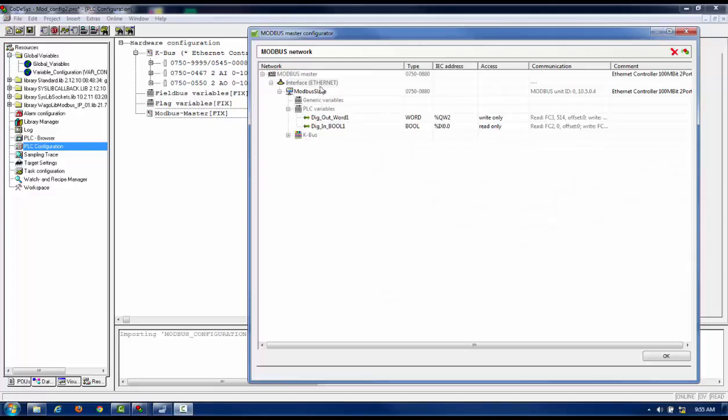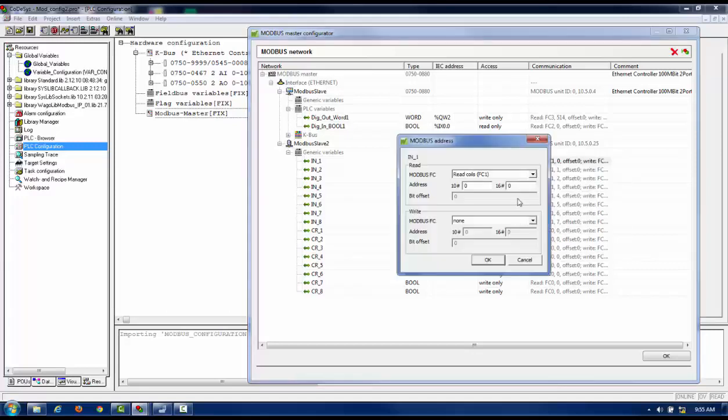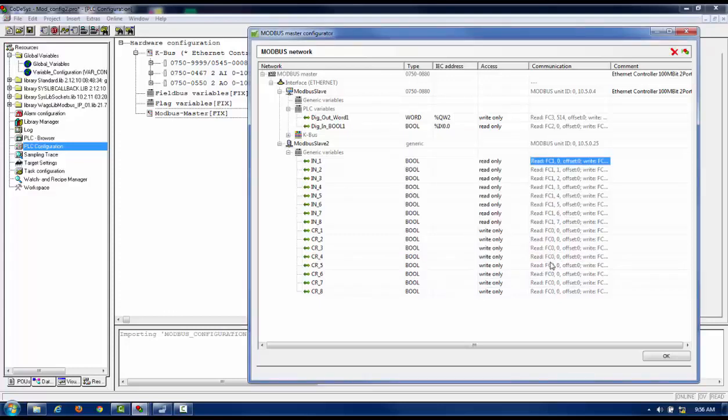So for example, in here, when I had the slave device and I just wanted to add it to this configuration by copying and pasting, then I can come in here and I can actually edit the information with regards to whether I want to read registers, coils, inputs, discrete inputs, single coil here on the right side, register, multiple coils, multiple registers, and so forth. So yeah, you can do additional stuff in here with regards to configuration.